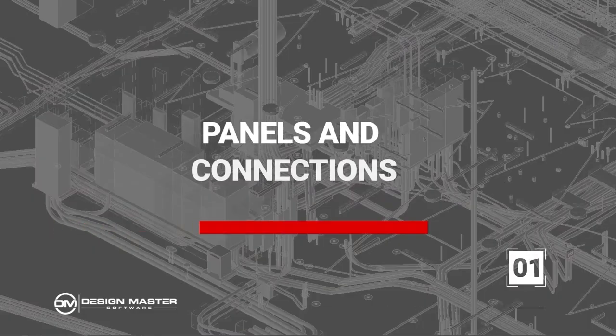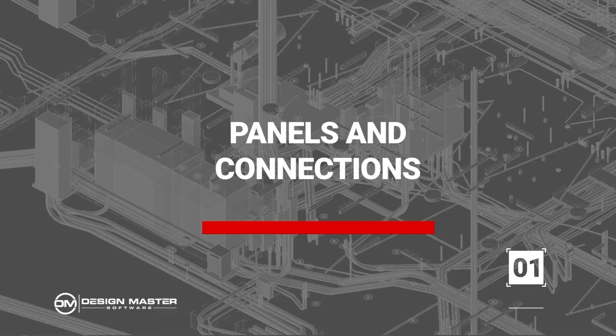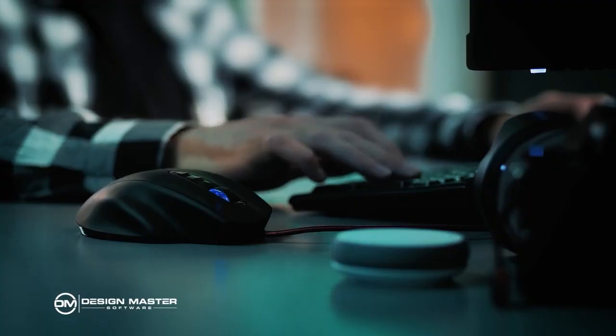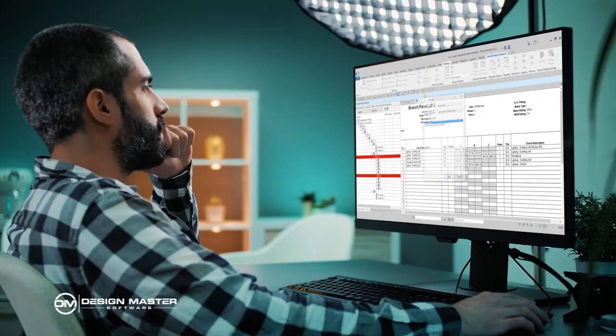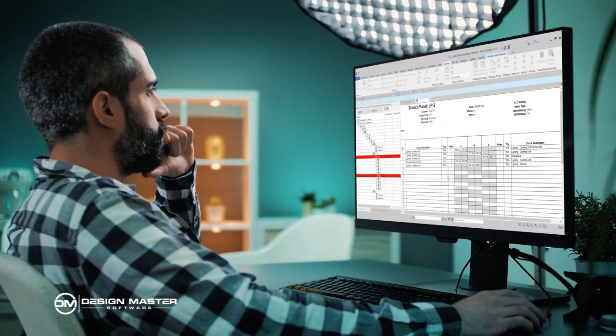So the first one, the panels and their connections to each other. If you're doing building information modeling, that's laying out your panels in your building, that's connecting your panels together. If you're doing that in something like Revit, you have all of those panels, you have all of those connections already made. You want to make sure that you're pulling those connections and those panels directly into whatever you are doing for your fault calculations.